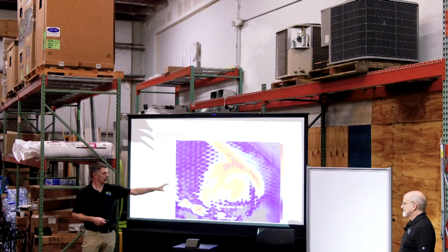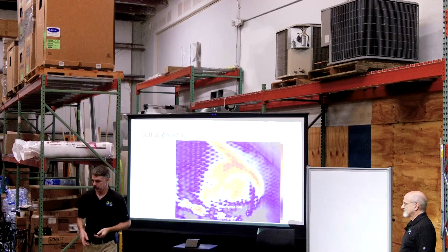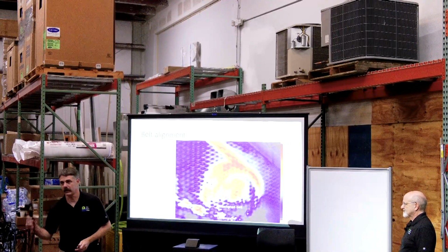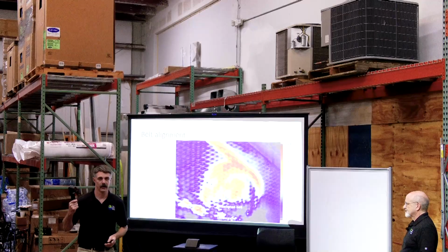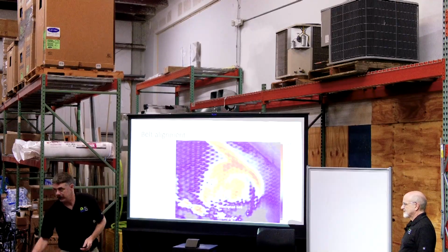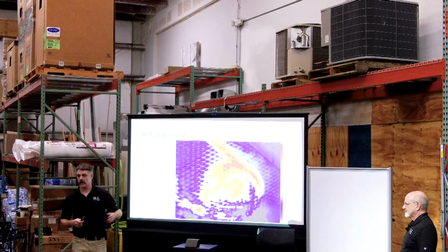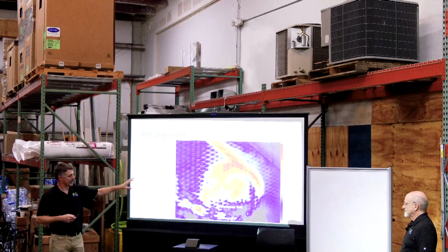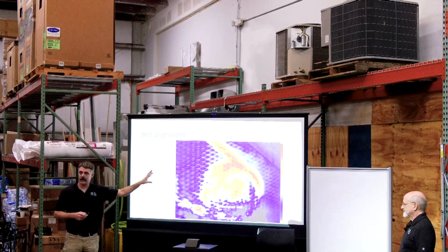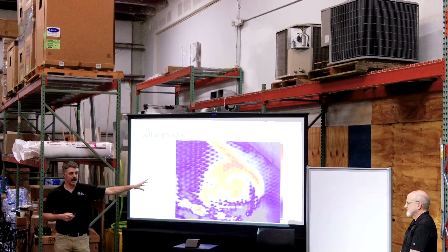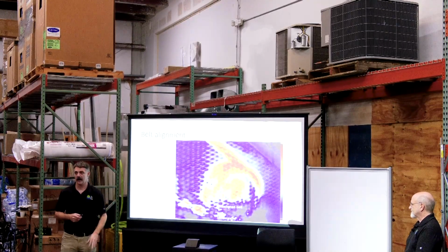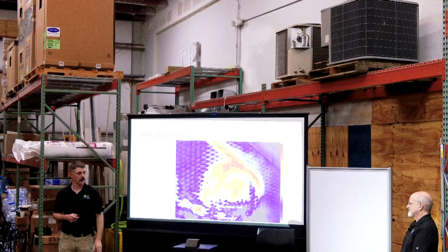So this is a really great, and this is where I mentioned putting these things inside of equipment and watching it wirelessly. Now I can put that in there and step back and watch it from across the room where I'm operating the equipment, but I can see that I've got a misaligned belt, and I can visually show that that belt is getting too hot. It's getting hotter than it should be. Right? And I can show that.